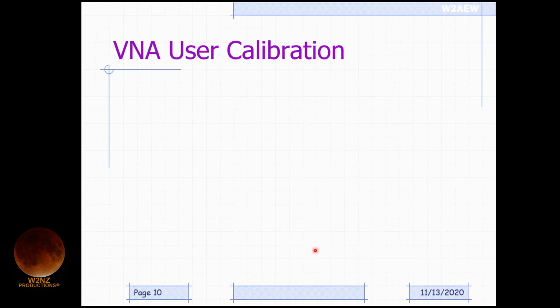Another thing that becomes confusing with VNAs is something called a user calibration. That's something you've got to do with a VNA, and we're going to talk about why. I can pick up my antenna analyzer, just use it and it works. Why can't I do the same thing with a VNA? There are a couple of different reasons. So why do we need to run what's called a user calibration on the instrument? Isn't it calibrated from the factory after they build it?